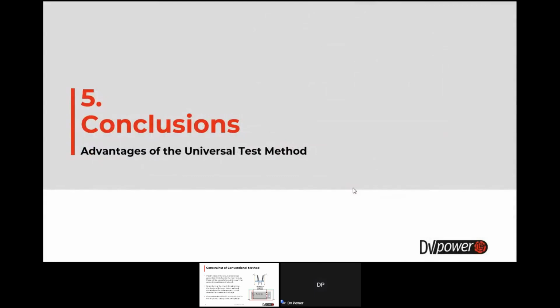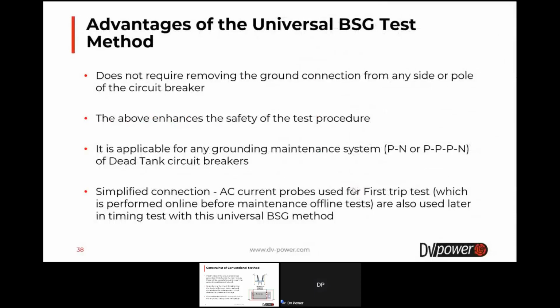In conclusion, I will list the advantages of this universal BSG test method. They are the following. This method doesn't require removing the ground connection from any side or pole of the circuit breaker. This enhances the safety of the test procedure. This method is applicable for any grounding maintenance system, PN or PPPN, of dead tank circuit breakers. And the connection for this method is simplified since AC current probes are also used for the first trip test, which is performed online before maintenance offline tests. So these AC current probes later can be used in the timing test when this universal BSG timing method is applied.